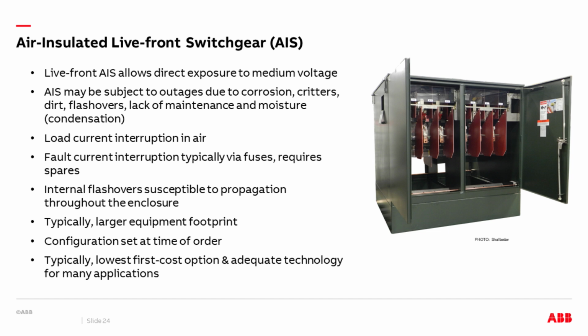Air-insulated switchgear has been around for a long time. It has a very successful history in the field, and it works great in many environments. But for different reasons, for different utilities and in different environments, sometimes they have chosen to replace this. This type of gear uses, obviously, air for the insulation.